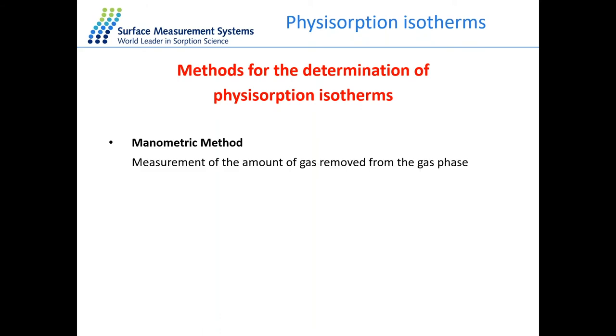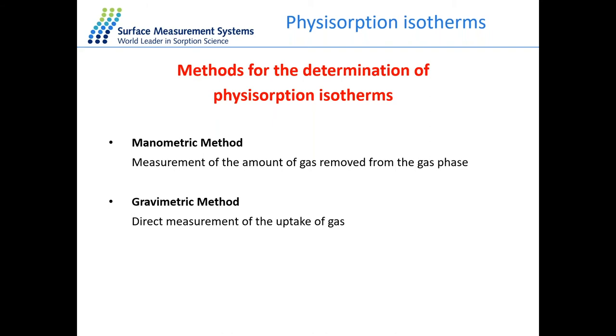What methods can we use for determination of physisorption isotherms? The most common is the manometric or volumetric method, used for collection of liquid nitrogen adsorption isotherms, where we measure the amount of gas removed from the gas phase. The other method, which is a direct method, is the gravimetric method. The gravimetric method involves direct measurement of the uptake of gas or vapor molecules. The focus of this talk is on outgassing conditions and adsorption isotherm collection using the gravimetric method.